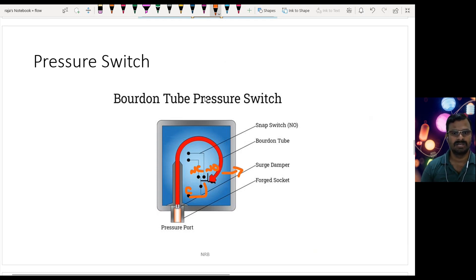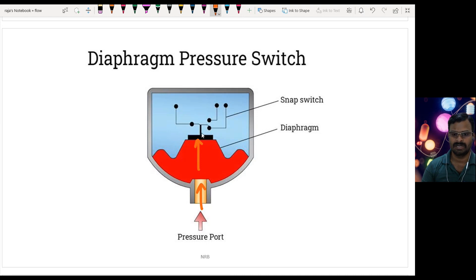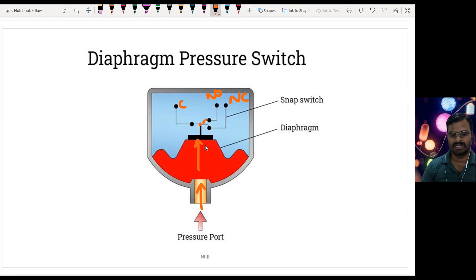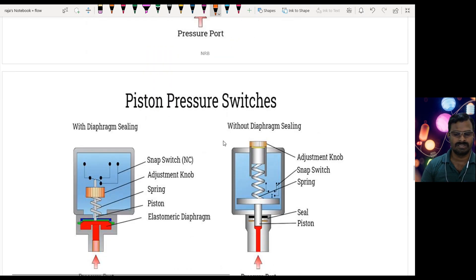The diaphragm pressure switch uses a diaphragm instead of a Bourdon tube. Pressurized liquid is sent in, pushing the diaphragm upward, and the contact moves with it from NC to NO. The common terminal changes to NO when enough pressure is applied against the diaphragm. The contact closes and this signal is given to the PLC so it can take a decision according to the program.